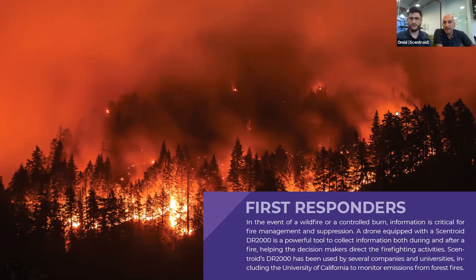And then sensor measurement stability. For each sensor, we have published accuracy, lower detection limit, range, and everything. We've done a lot of improvements on the sensor stability, so we can share some findings that third parties like universities have done comparing our instrument against other electrochemicals. When they compare to a station, for example NO2 or ozone, compared to a full US EPA station, we're getting R squared values of the comparison being like 96%, in the low PPB level, like from 3 to 15, 20 PPB. We're seeing the same kind of trend in our analyzer as we see in our station sensors, in the 15 PPB range, which is really amazing.